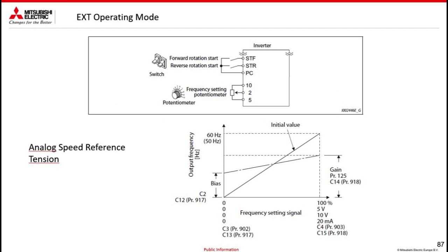Another mode of operation is by means of analog set points. So we will simply wire STF rather than STR, and we will wire our potentiometer between 10, 2 and 5, where I remind you that 10 is plus 5 volts, 5 is the common 0 volt, and 2 is my reference signal. So by varying the voltage, the output frequency will vary from a minimum set to a maximum set. By default it is from 0 to 50 Hz.